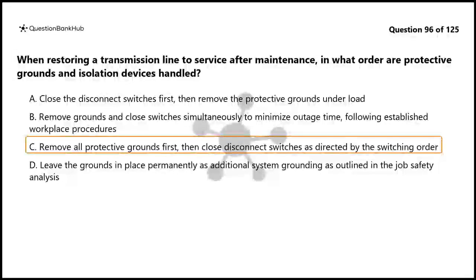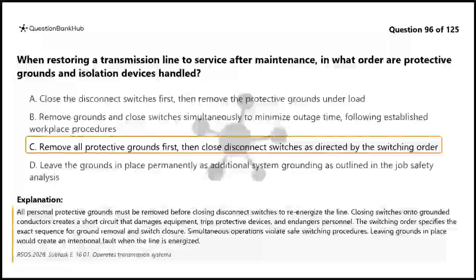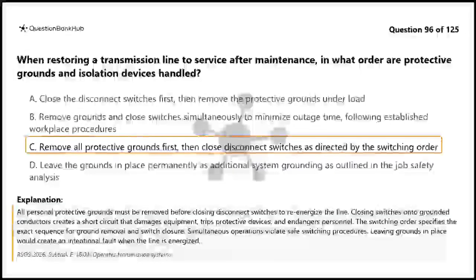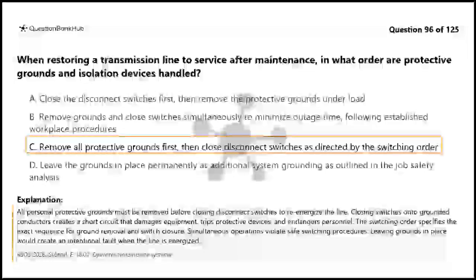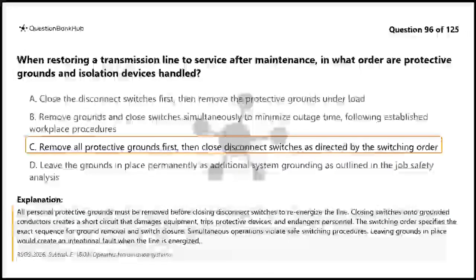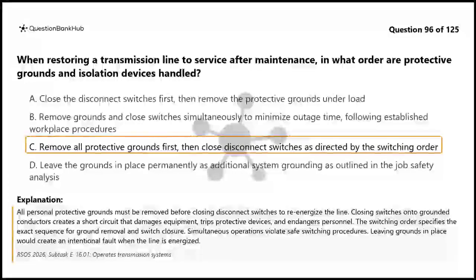The correct answer is C. All personal protective grounds must be removed before closing disconnect switches to re-energize the line. Closing switches onto grounded conductors creates a short circuit that damages equipment, trips protective devices, and endangers personnel. The switching order specifies the exact sequence for ground removal and switch closure. Simultaneous operations violate safe switching procedures. Leaving grounds in place would create an intentional fault when the line is energized.